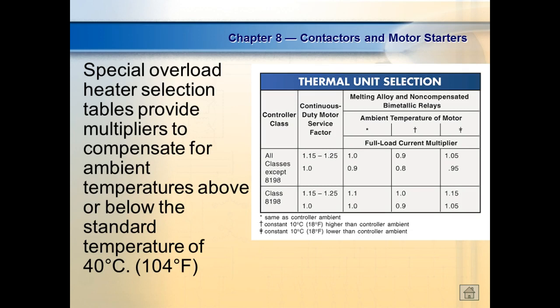So it says for every same as controller, these are our multipliers. So controller class, ambient temperature. So what it's saying is full load current. This asterisk right here says constant 10 degrees higher. So that means I need to take my full load current and multiply it by 90%, right? Y'all understand that? If we're running it 10 degrees lower, which would be this guy right here, then I can actually get 1.05. Does that make sense? Yes, ma'am.